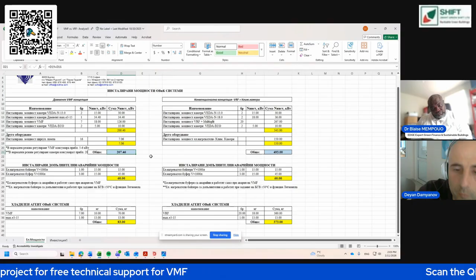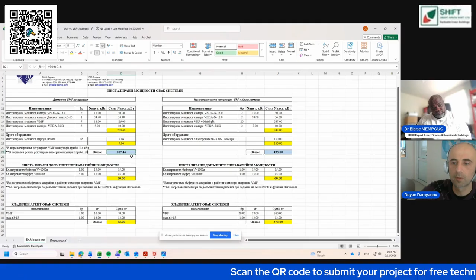It's in Bulgarian, but I will explain. Here we have 7 VRF units, additional 2 big ventilation units, and additional 2 smaller ventilation units. So the total installed power input for this project, including the circulation pumps, is 207 kilowatts. Then the total quantity of refrigerant with the VRF concept on this project is 83 kilograms, but all of it is outside the building, no refrigerant inside.